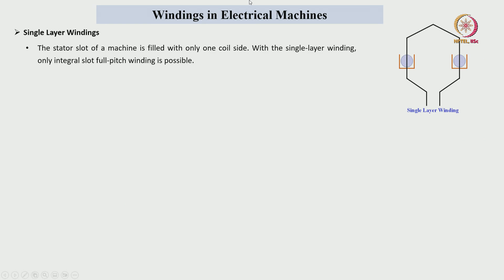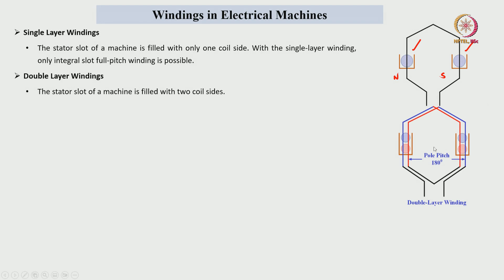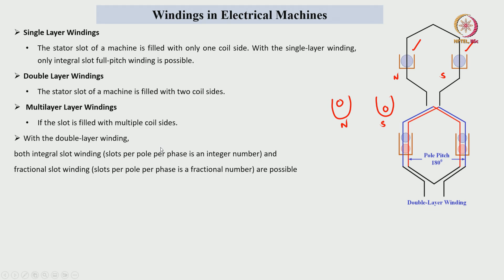In single layer winding, each slot consists of one coil side — one coil side under the north pole and one under the south pole. In double layer windings, each slot consists of two coil sides: the blue color at the top side and the red color at the bottom side. To make the winding symmetrical, the top side conductor is always connected to the bottom side conductor under the south pole. This minimizes leakage flux and achieves symmetrical winding distribution.